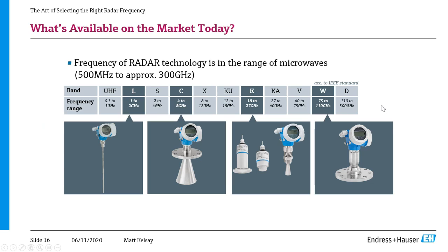Radars that operate within the same frequency band, if you're looking at the K band, whether that's 18 or 27 gigahertz, are going to have very similar characteristics. Different manufacturers might use a slightly different frequency within that band, but for the most part, if it's in the same frequency band, like a K band, the characteristics will be fairly similar. However, as you move from one band of radar to the next, you see drastic differences in the characteristics, which is what we're going to cover today. For the last 15 years or so, K-band radar was considered high frequency. That 26 gigahertz was the highest available on the market, and it was used for nearly all applications. However, within the last couple of years, W-band radars have become available and are now what's considered high frequency and are becoming more and more popular. We'll cover the differences between all of these frequency bands and then when you might use one versus another.